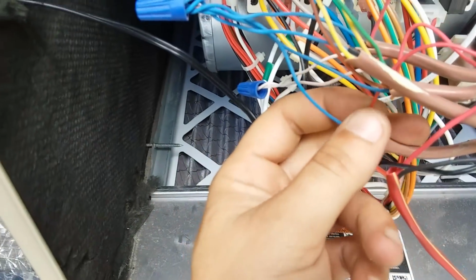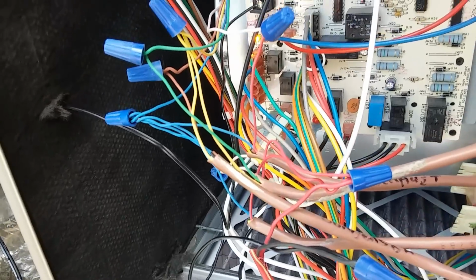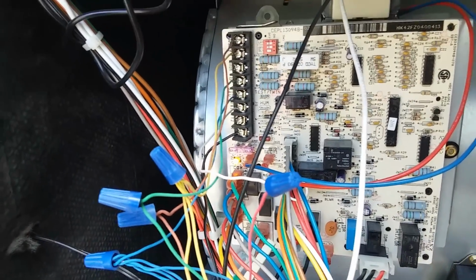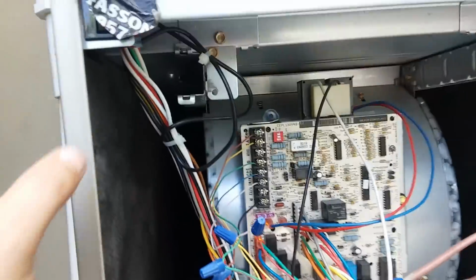and the primary thermostat. So on the secondary thermostat, what they've done is, see how it only has the red in common? These are placebo thermostats. So this is just going to the thermostat, I'm sorry to say this, but mind fuck them into thinking they have control over the temperature in their room, but they don't. But this guy does have the controls. So he's in 123, which means he controls 124.